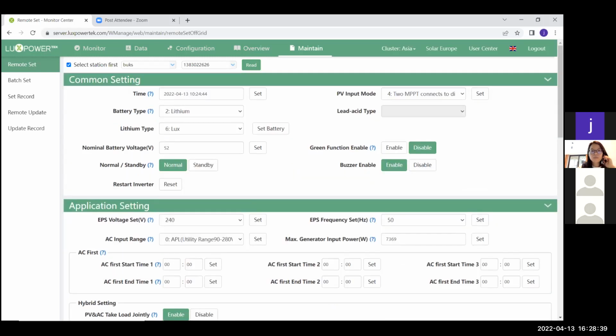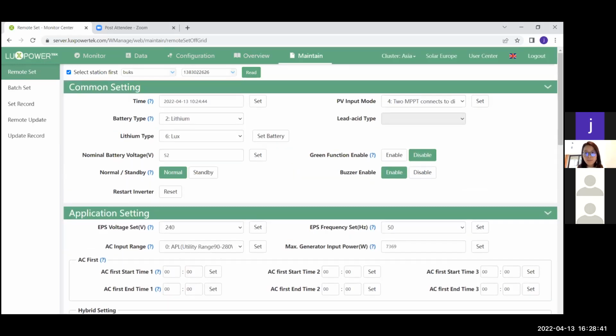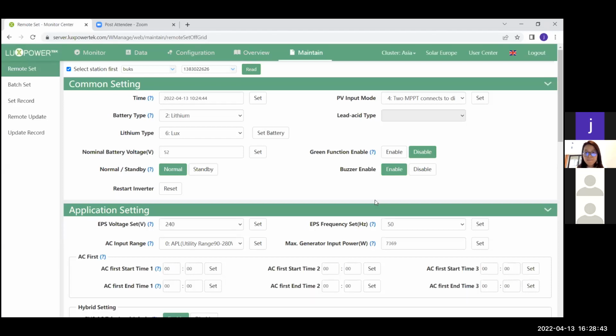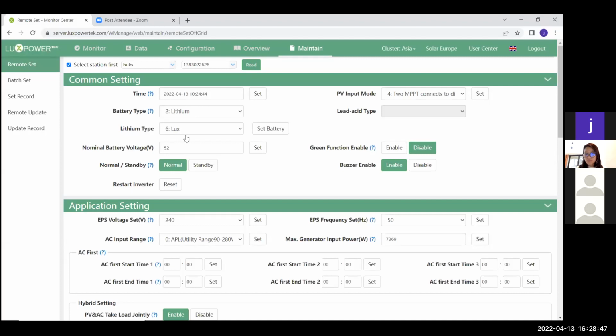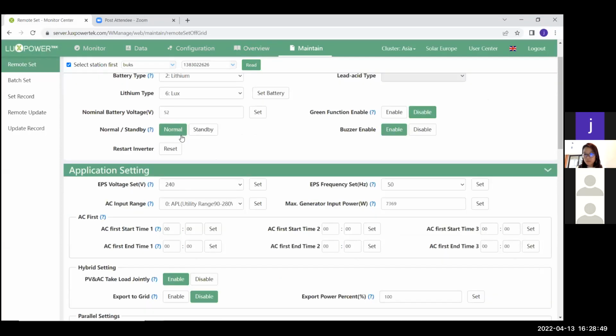Can everybody still hear me? My screen just said internet connection. Okay, it's fine. So from here on, settings-wise, normal and standby, you're always going to select normal. Green function, you always disable for a unit, because in green function mode, if your inverter pulls less than 60 or 70 watts for, I think, half an hour, your machine will switch off. So green function, you always disable.